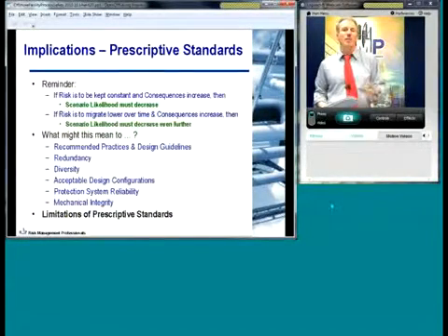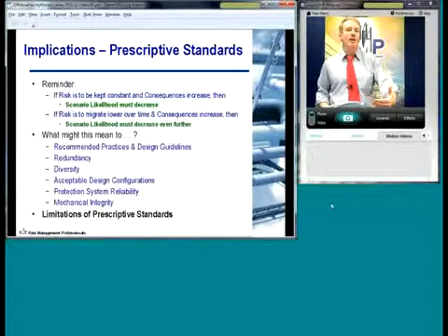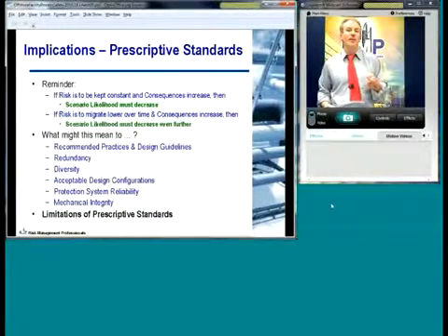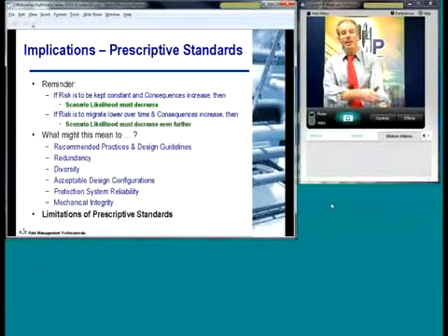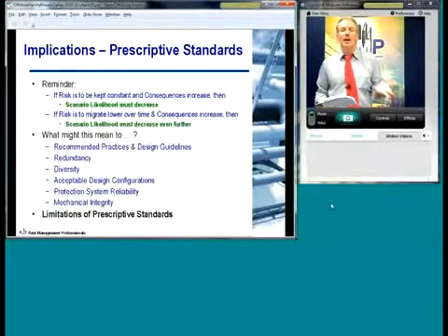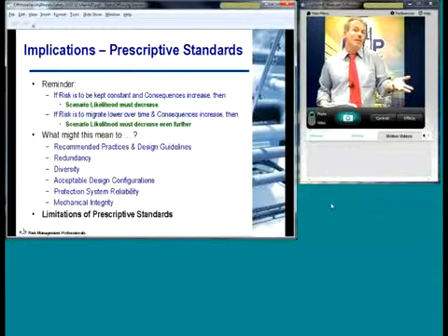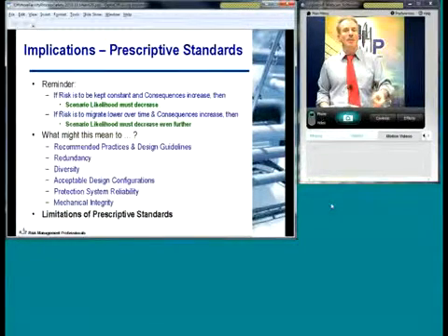Now, what I also want to share with you to tie together this platform safety shutdown system effectiveness study, the evolution of protection systems, safety integrity level requirements, et cetera, is just a reminder that if you're trying to lower the bar on what risk is acceptable to your operation, if the consequences are going up or you want to lower risk, you're going to have to really look at scenario likelihood. That's where all these SIL categories, the SIS and HIPS systems come into play. All those are important to consider when you're looking into those issues. What that means is if you're looking at design guidelines, redundancy issues, the diversity of your system, what are acceptable design architectures, and also the overall reliability of your protection system, and folding that back into your mechanical integrity program that's part of SEMS, this all rolls together to try to make sure that the safety systems are operational and have sufficient reliability.